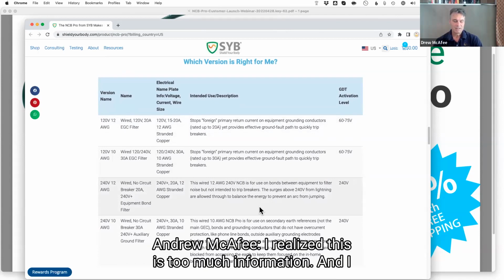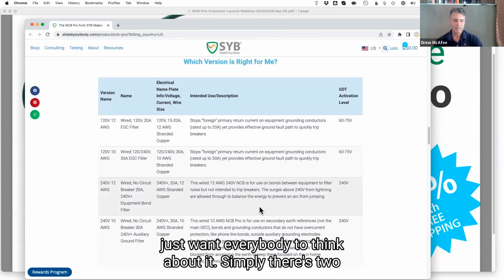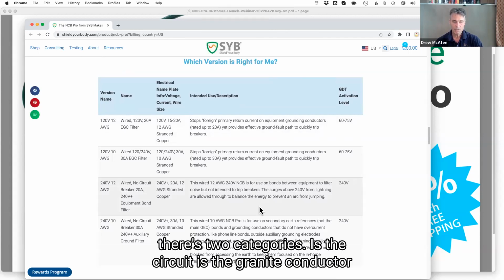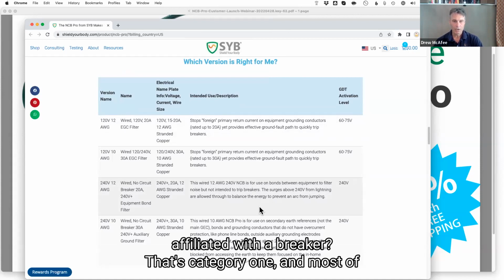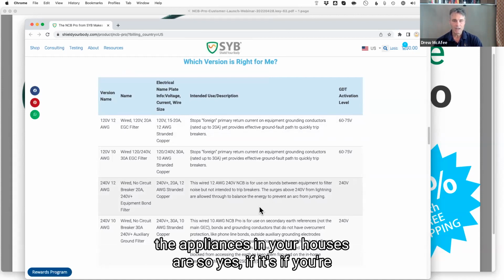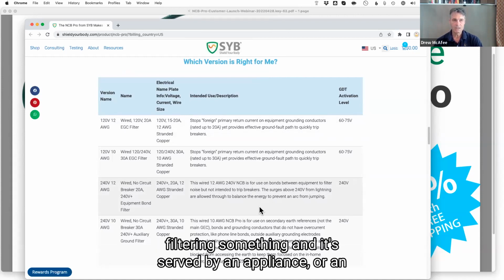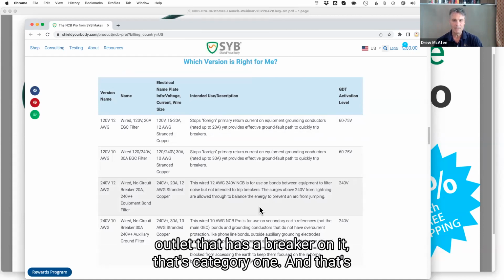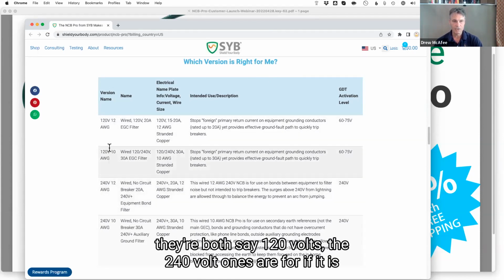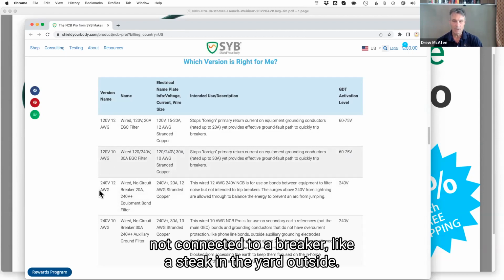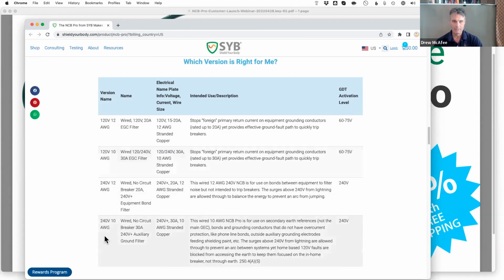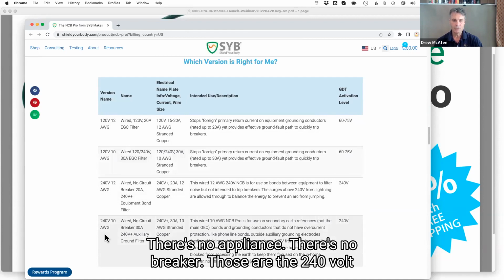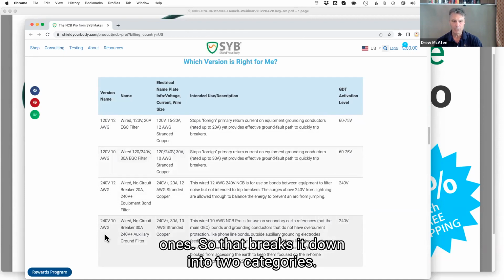Yeah, I realize this is too much information, so let's simplify. There's two categories: is the grounding conductor affiliated with a breaker? That's category 1, and most appliances in your house are. So if you're filtering something served by an appliance or outlet with a breaker, that's category 1 - the 120 volt versions. The 240 volt ones are for when it's not connected to a breaker, like a stake in the yard outside - no appliance, no breaker. So that breaks it down into 2 categories.